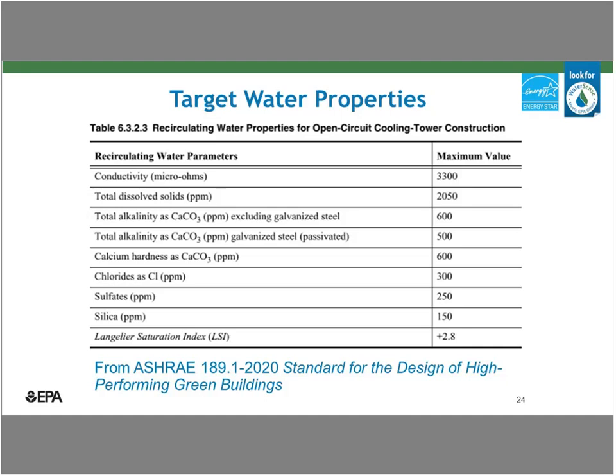2,050 divided by 1,000 is approximately 2. If your incoming water has a TDS of 200, then you should be able to achieve a cycle of 10. So your treatment vendor should take regular samples of your incoming water quality and cooling tower water to help you identify your targets. And if they aren't providing this information, be sure to ask them to.